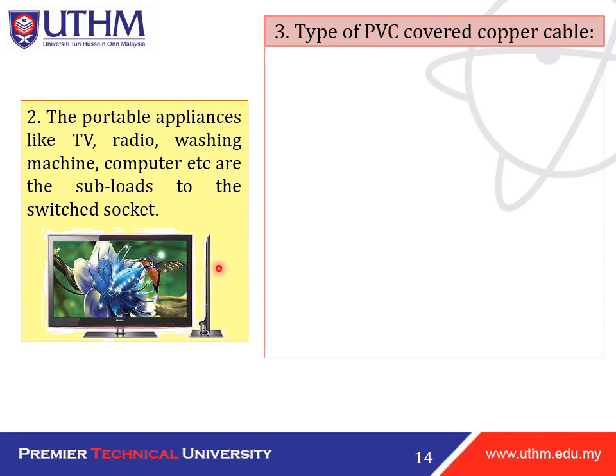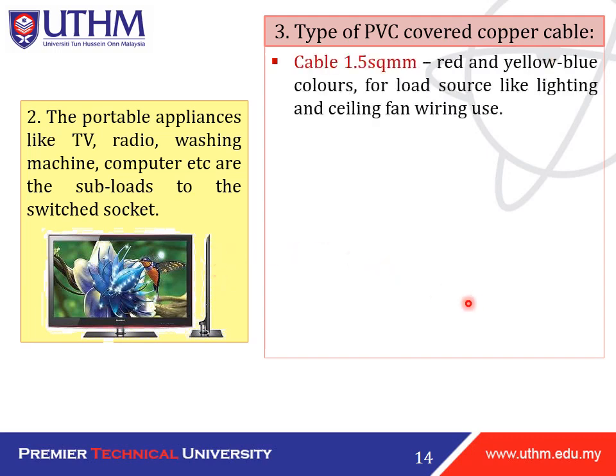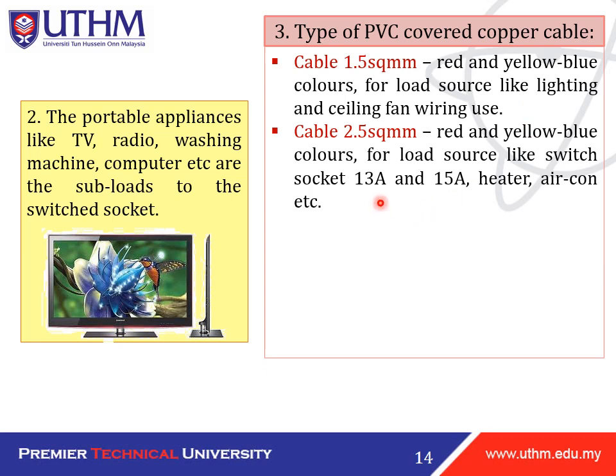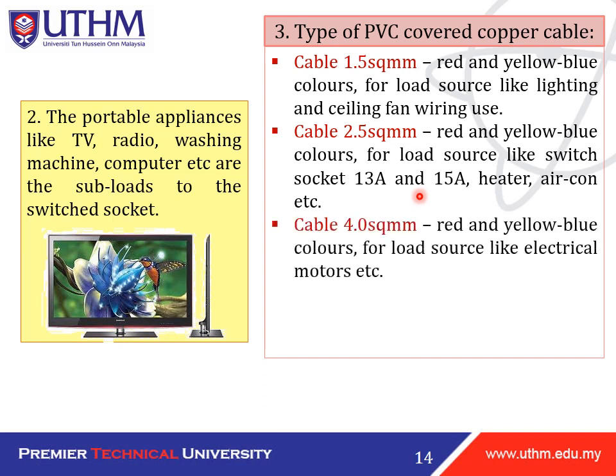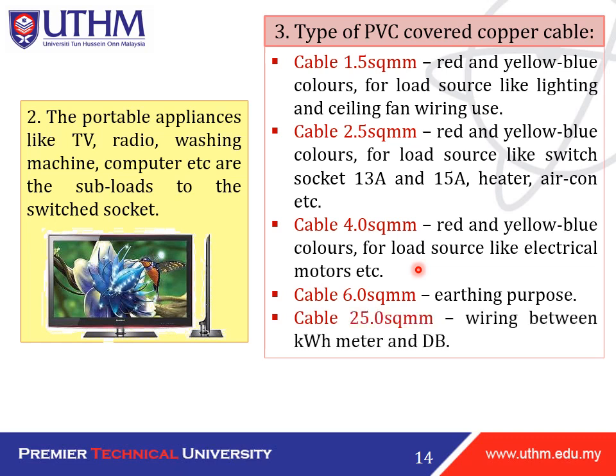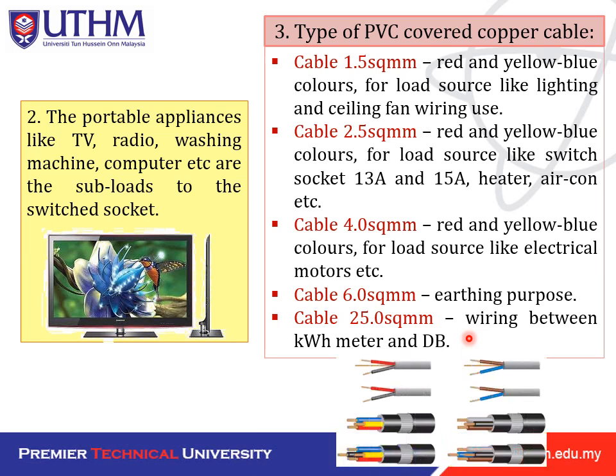And then we have the type of PVC covered copper cable. We have cable 1.5 square millimeter, red, yellow and blue colors, for load sources like lighting and ceiling fan wiring. And then we have cable 2.5 square millimeter, red, yellow and blue colors, for load sources like switch socket 13 amp and 15 amp, heater and aircon. And then we have cable with 4 square millimeter, red, yellow and blue colors, for load sources like electrical motors. And then we have cable 6 square millimeter for earthing purpose. And finally, the cable with 25 square millimeter for wiring between kilowatt hour meter and DB. Okay, this is the picture of the cable.